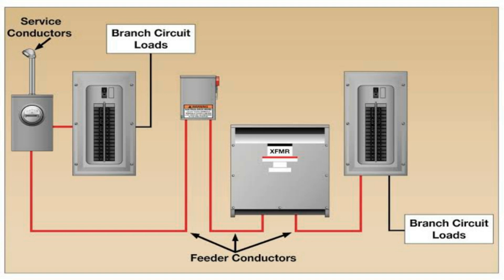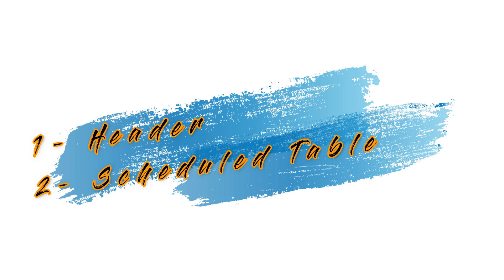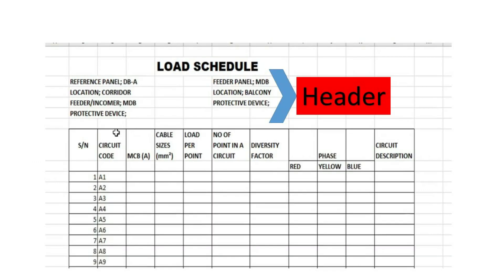To achieve this, a proper load schedule must comprise of two things. The first is the header, and the second is the scheduled table. Although their composition is based on personal preference, they must be able to express the panel protective device, the cable size, and the diversity factor.